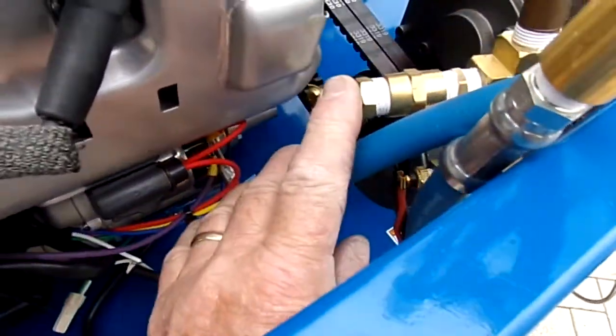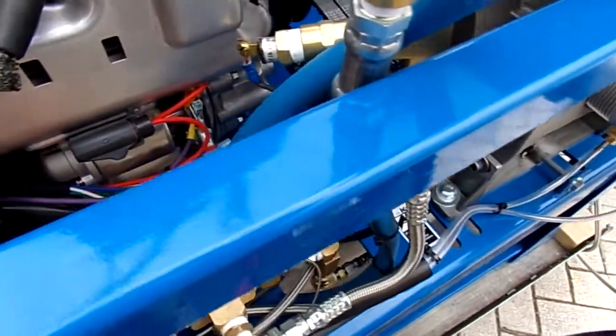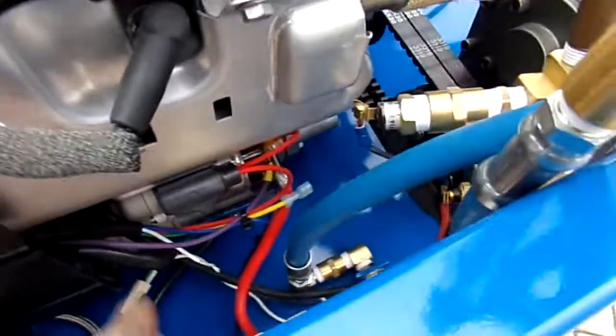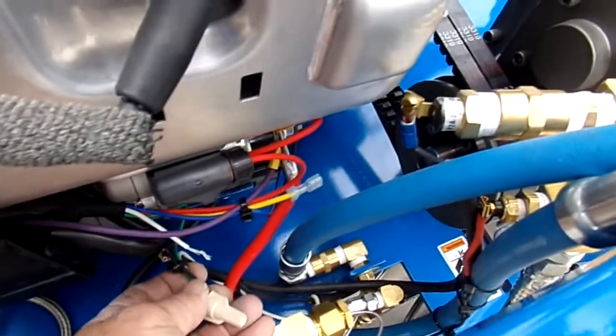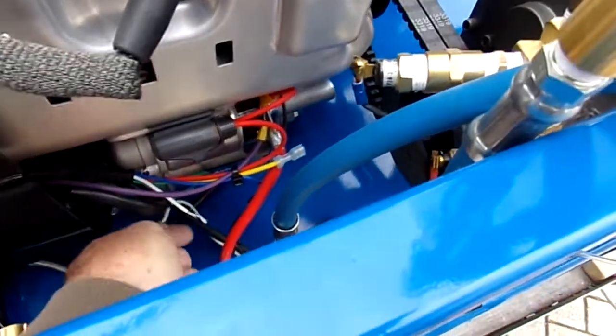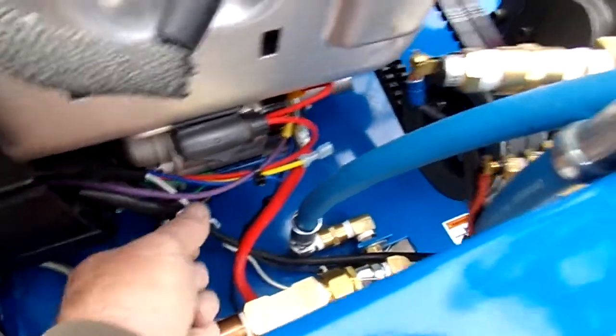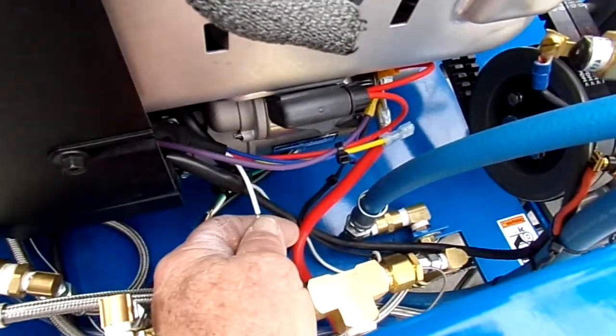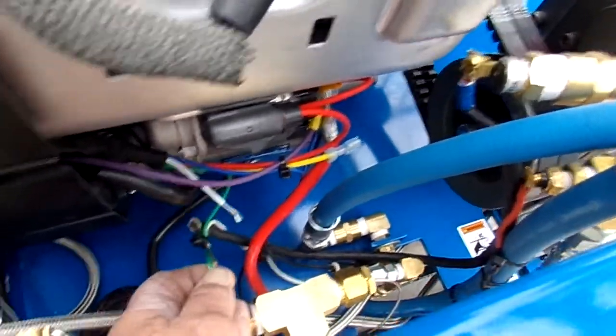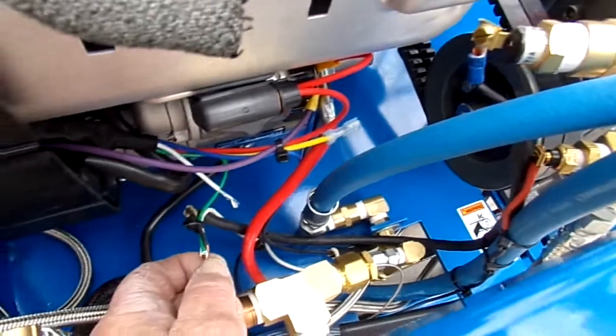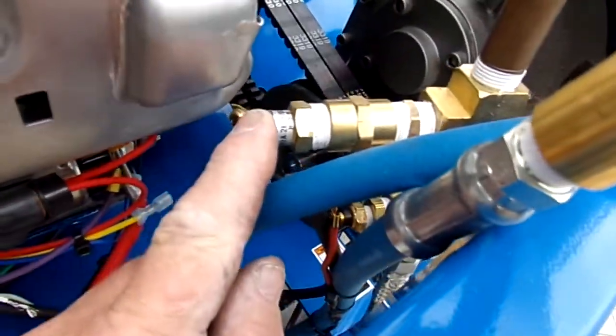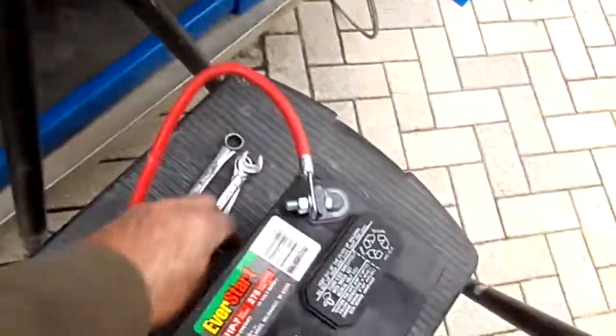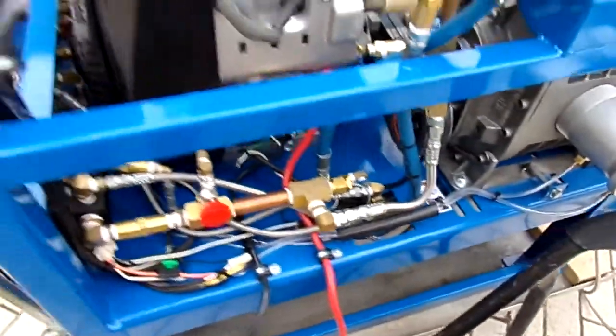You've got your high limit 285 shutdown. This white wire is going to be connected to these group of wires right here. So that will be connected, and that's your shutdown. This is your shutdown wire to your magneto, and the green is your low oil sentry. The other one is going to this, and the other one is to your waste tank.